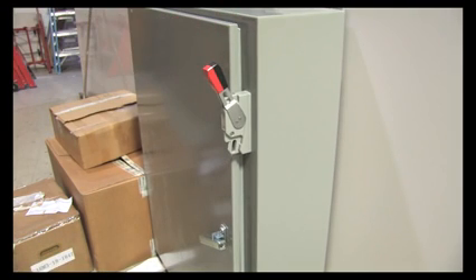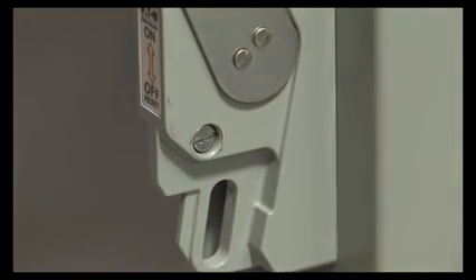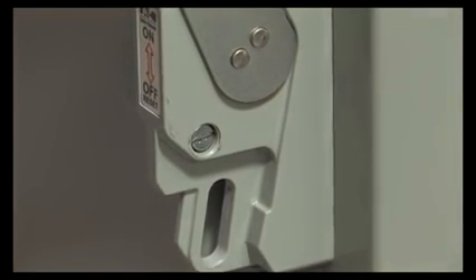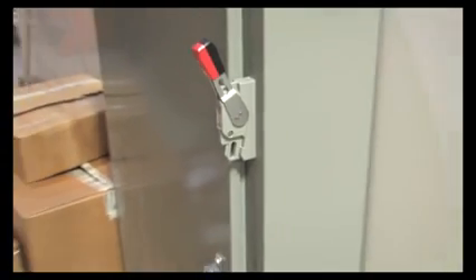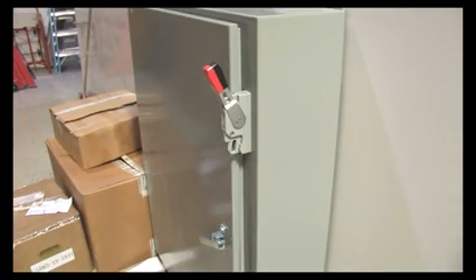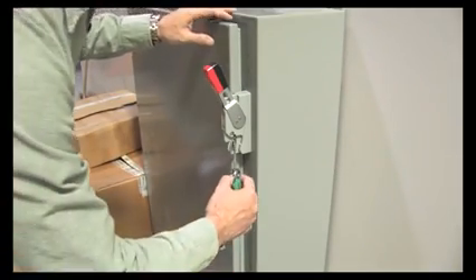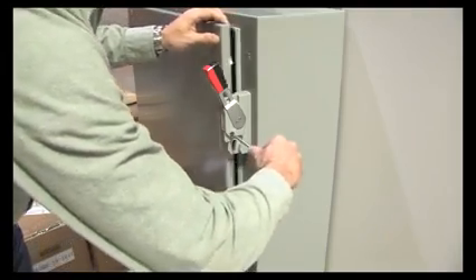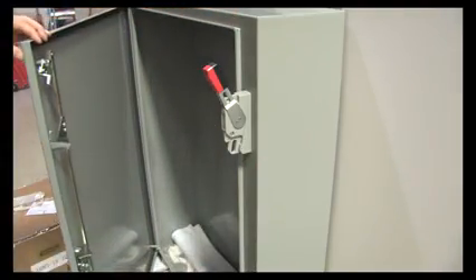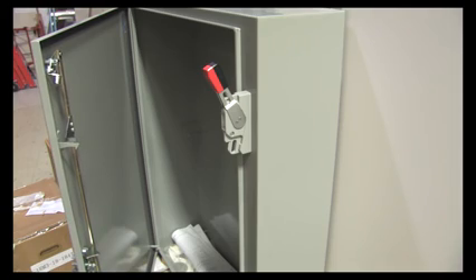There are times, though, when it's necessary to access the cabinet while the power is on. Maybe you need to do some diagnostics or some testing. In that case, these are designed so you can bypass or defeat the normal operation of the switch. On this one, you stick a screwdriver in here and twist, and it releases the catch so you can open the door. Beware that you are responsible for any liability if you defeat the operation of one of these devices, and it's assumed that you are fully aware of the OSHA requirements for things like arc flash and personal protective equipment.